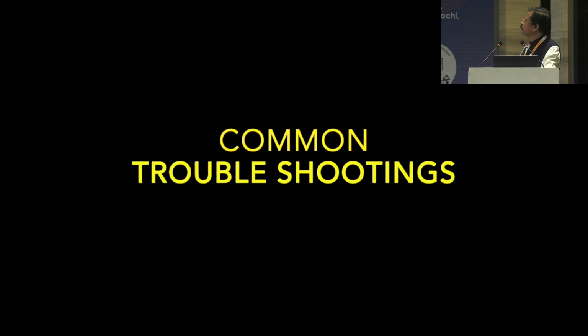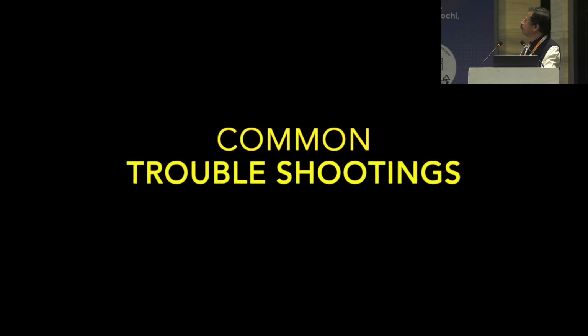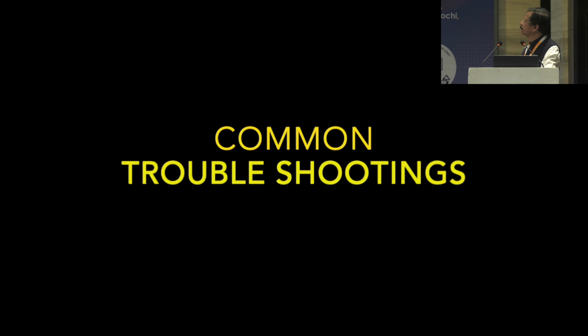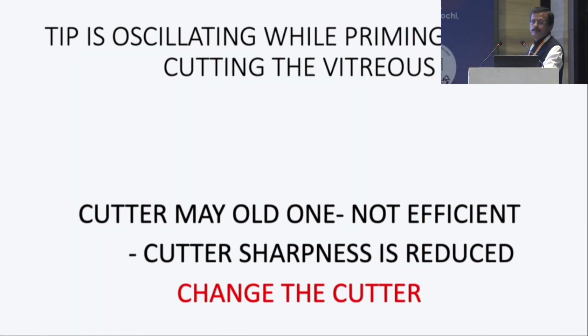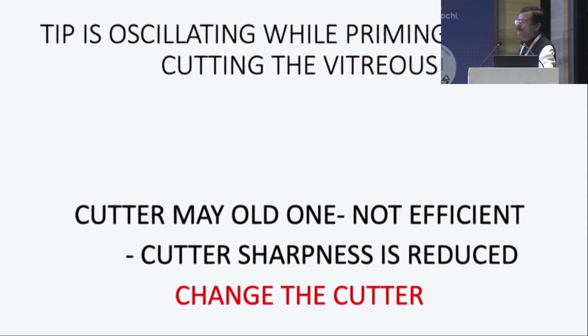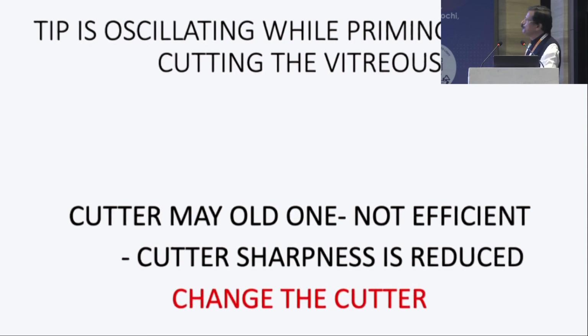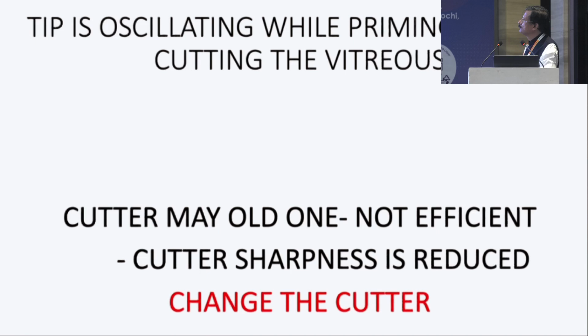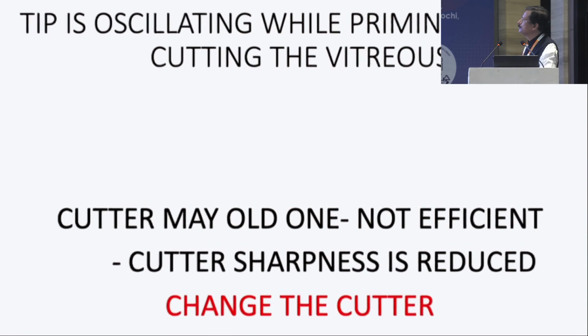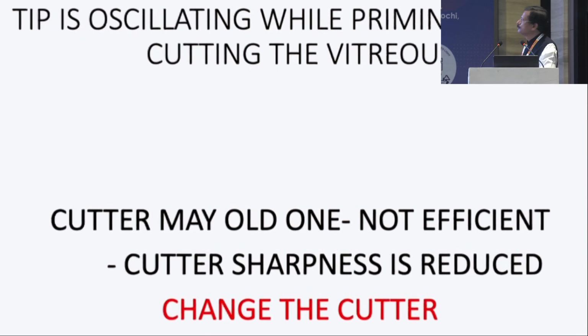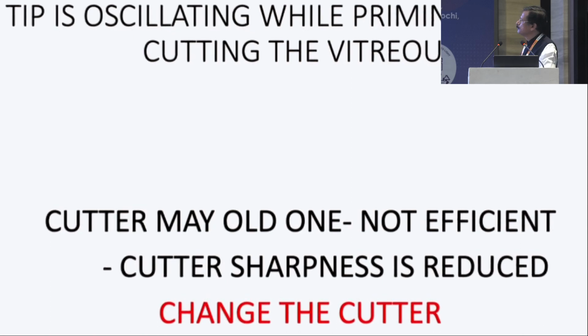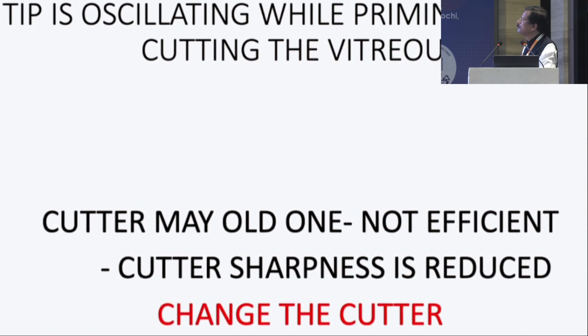To check the cutter, you have to see the tip of the cutter. It will be oscillating to and fro. That means it is cutting correctly. Most common problem is when you are priming, the cutter is oscillating, but when you are actually cutting the vitreous, it is not cutting. Probably the cutter may be old and has lost its efficiency, or the cutter sharpness is reduced. The solution is you have to change the cutter.